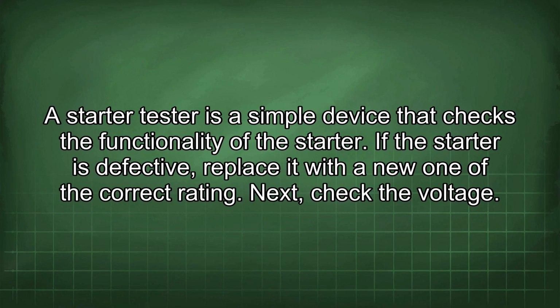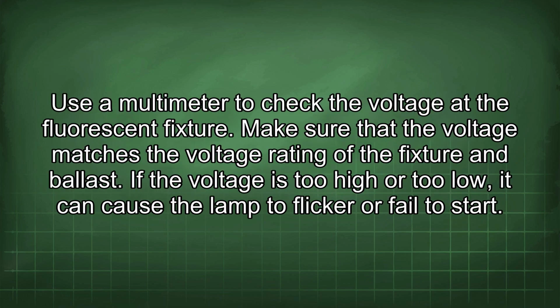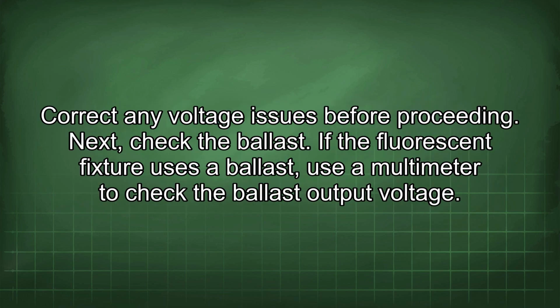Next, check the voltage. Use a multimeter to check the voltage at the fluorescent fixture. Make sure that the voltage matches the voltage rating of the fixture and ballast. If the voltage is too high or too low, it can cause the lamp to flicker or fail to start. Correct any voltage issues before proceeding.